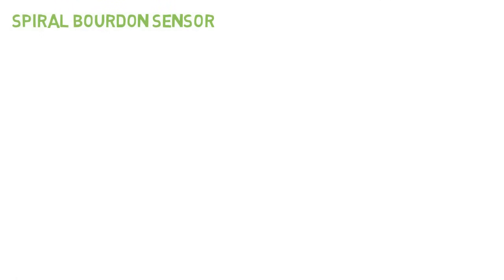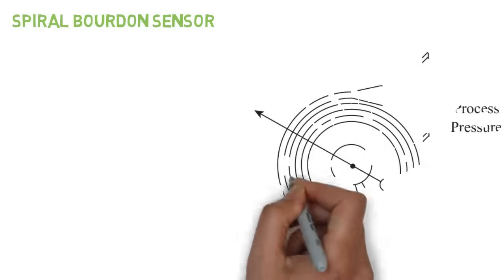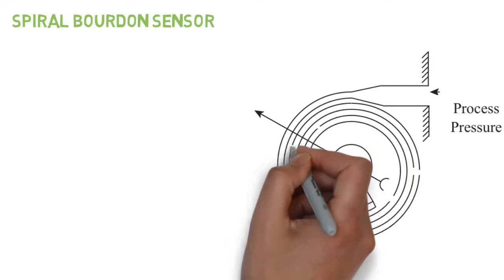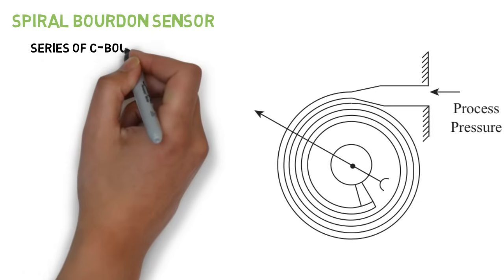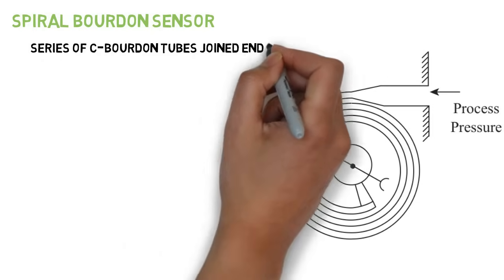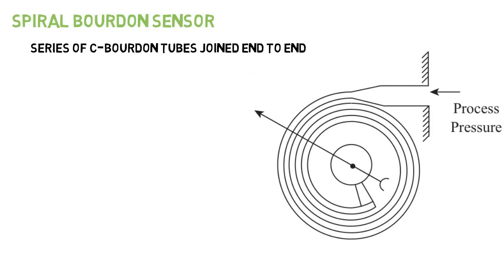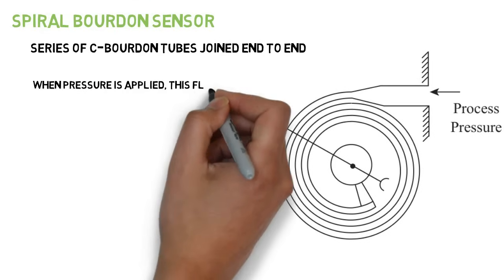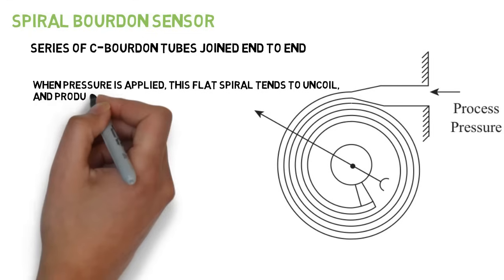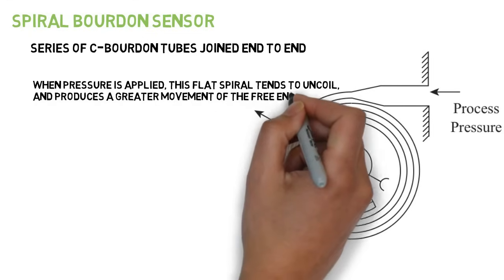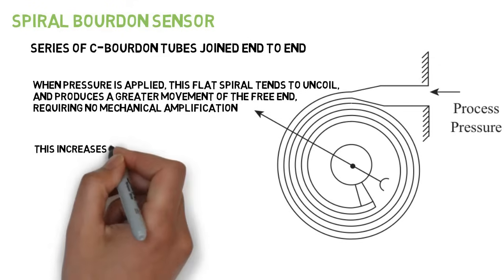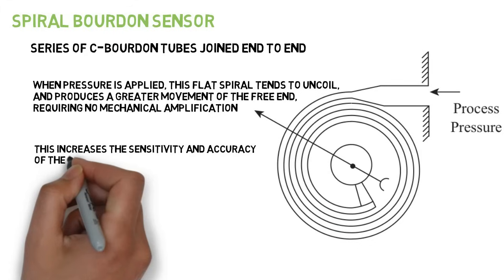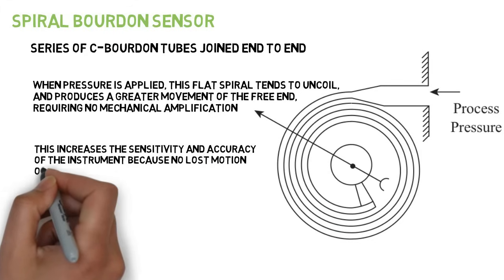Since the free end motion of the C type Bourdon tube is insufficient in some cases, the spiral type Bourdon tube is used. The spiral element is essentially a series of C type Bourdon tubes joined end to end. When pressure is applied, this flat spiral tends to uncoil and produces a greater movement of the free end, requiring no mechanical amplification. This increases the sensitivity and accuracy of the instrument, because no lost motion or friction is introduced through the links and levers.